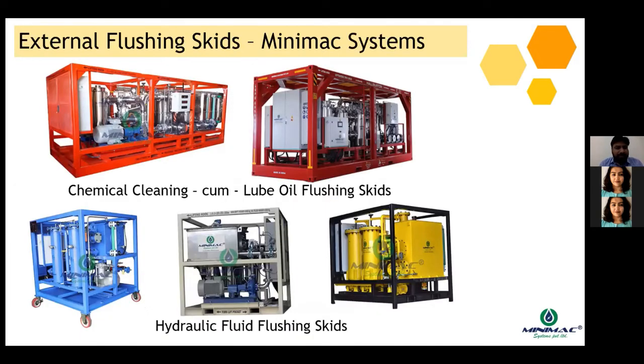Some photographs of external flushing skids. We have seen at multiple sites that the professionals fabricate the flushing skids at the site. They lay down some ad hoc arrangements of loose pumps, filters, heaters, control systems at the site itself. And many times these sites are controlled under ISO norms for health, environment, and safety. And under those situations, such ad hoc arrangements are not approved by the end user or the site owner. So in these situations, you can go for standalone, external, combined systems, which can be used for flushing application.